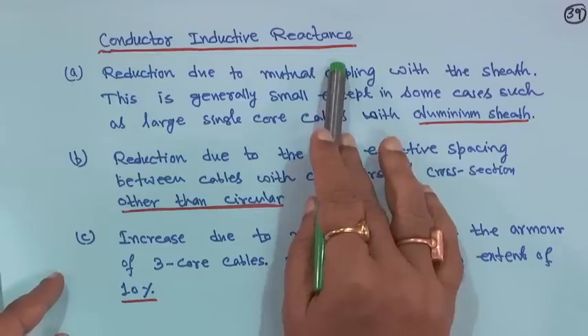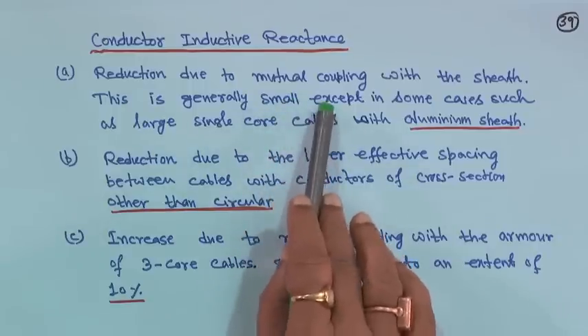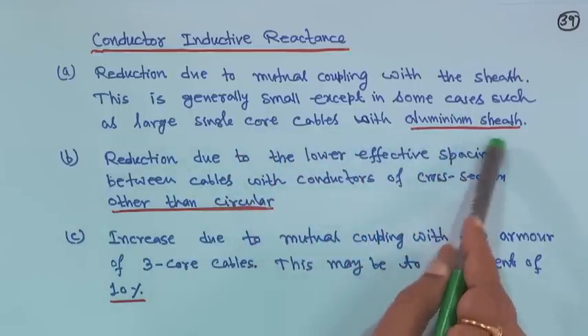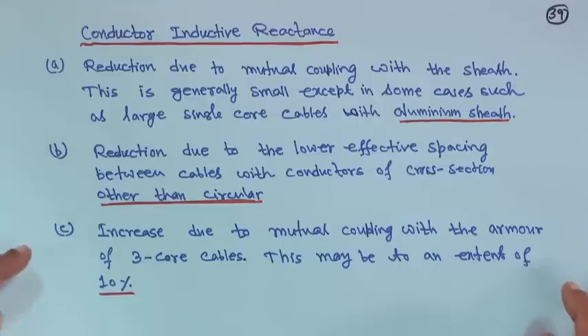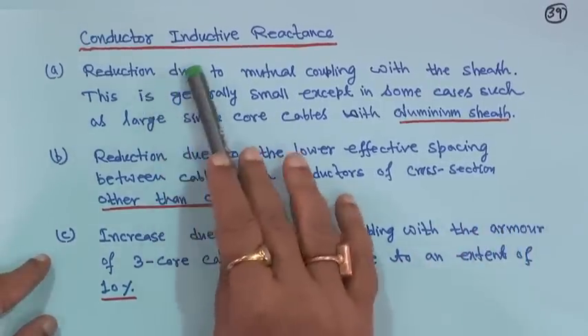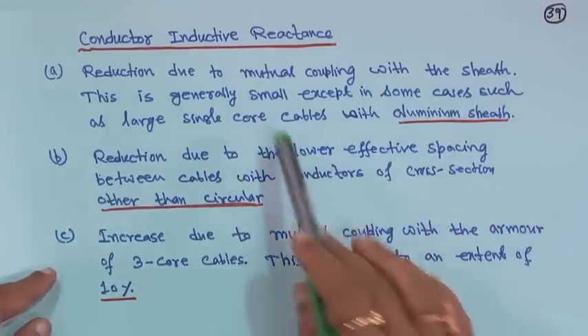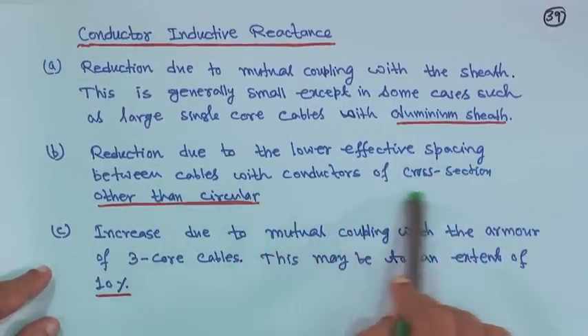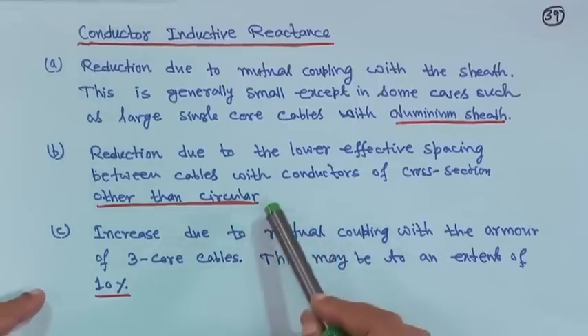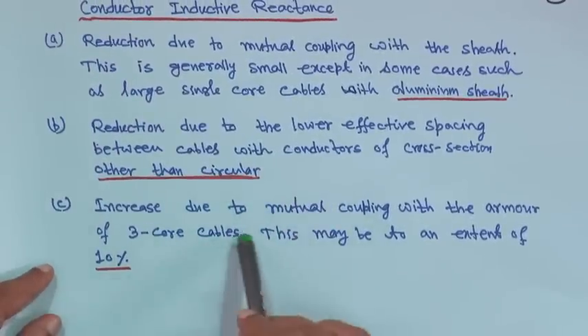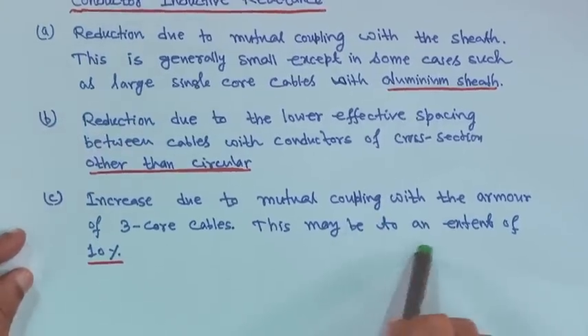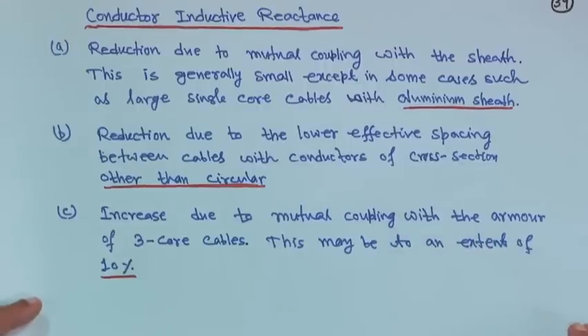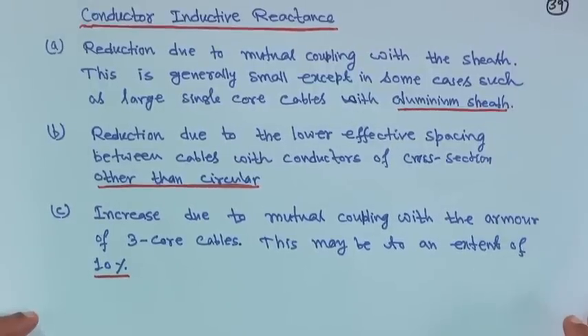Next is conductor inductive reactance. Reduction due to mutual coupling with the sheath is generally small, except in some cases such as large single core cables with aluminium sheath. Reduction also occurs due to lower effective spacing between cables with conductors of cross section other than circular, but generally circular conductors are used. Increase due to mutual coupling with the armour of 3-core cables may be to an extent of 10 percent — naturally if mutual coupling is there, inductance will increase.